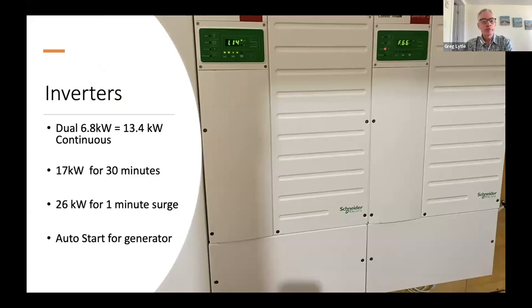With the new system, we upgraded the inverters, as I mentioned. So we've now got two dual 6.8 kilowatt inverters to give us a total of 13.5 kilowatts continuous. For short periods of time, the system will support 17 kilowatt outputs, or 26 kilowatts for surge supply. That's important when you've got heavy loads or momentary surges that you don't want the inverter to kick over and have to start the genset for just a transient load. So the systems work very well in those situations to supply our peaks.